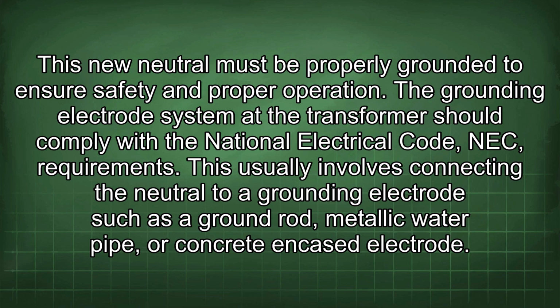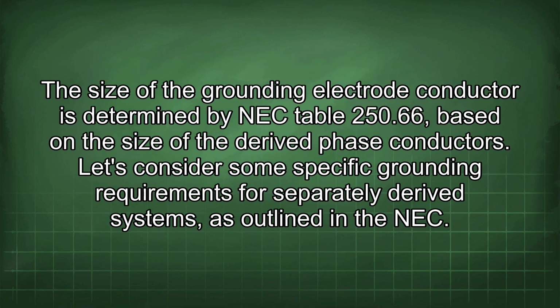The grounding electrode system at the transformer should comply with the National Electrical Code (NEC) requirements. This usually involves connecting the neutral to a grounding electrode such as a ground rod, metallic water pipe, or concrete encased electrode. The size of the grounding electrode conductor is determined by NEC Table 250.66, based on the size of the derived phase conductors.